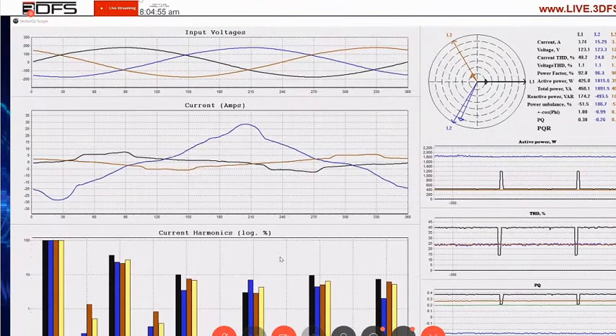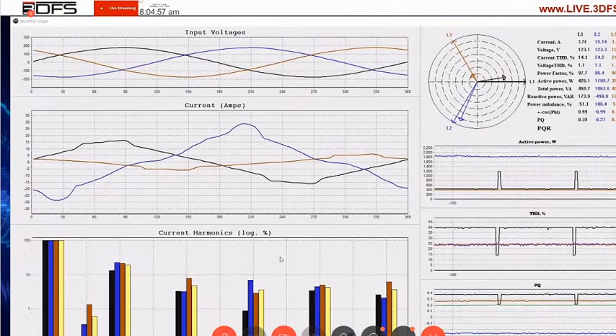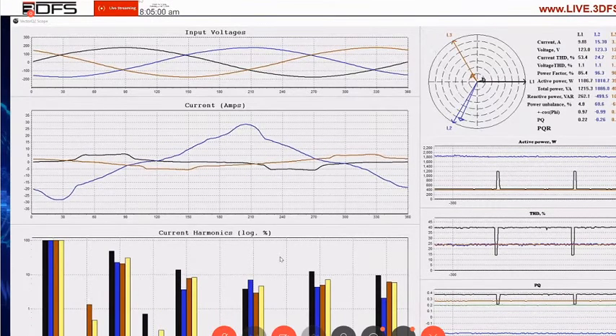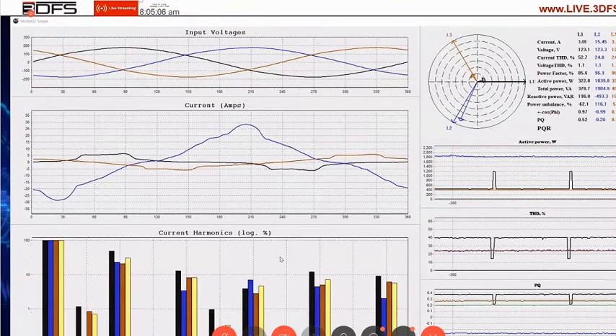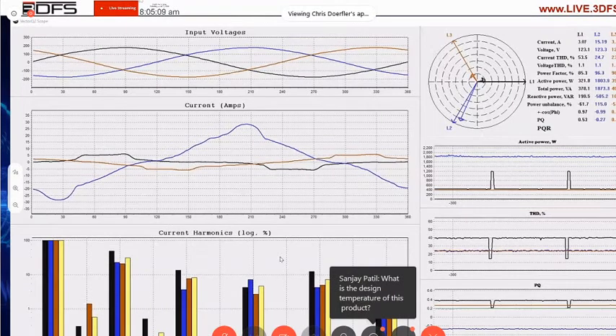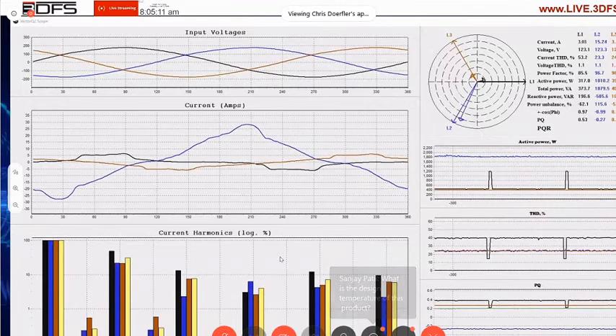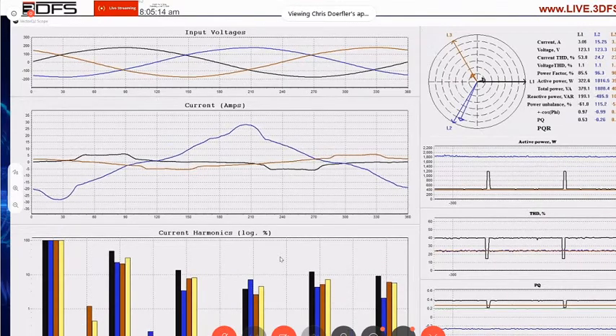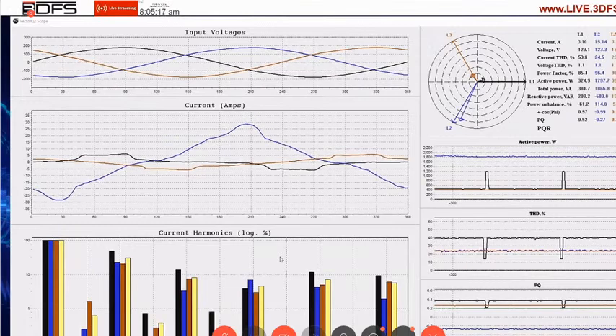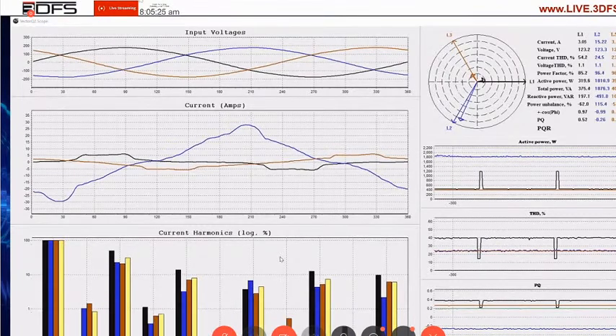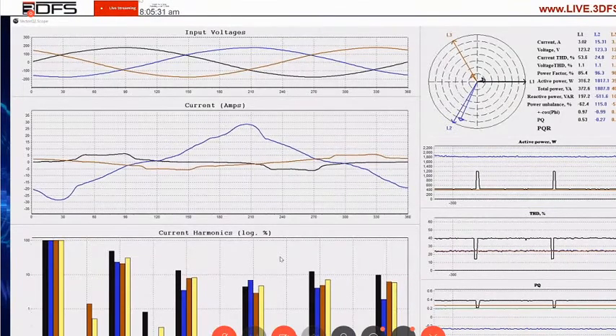The best analogy is if you squeeze a balloon, it doesn't pop - it goes through your fingers, the air has to go somewhere. When you generate electricity and put it onto the grid, that energy has to go somewhere. If it doesn't go to the load, it gets released as heat or vibration. That's why with active filters, not only do you put the filter in, but you also have to add air conditioning and large fans - there's no efficiency there. This device has just 2 fans on the side.